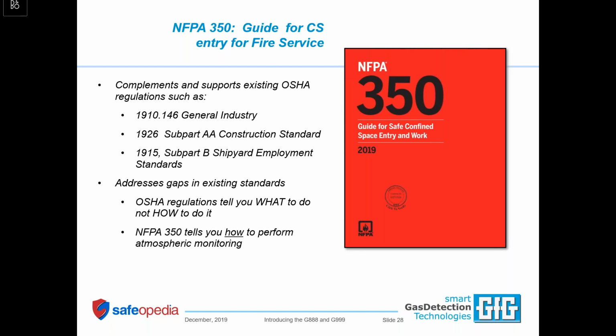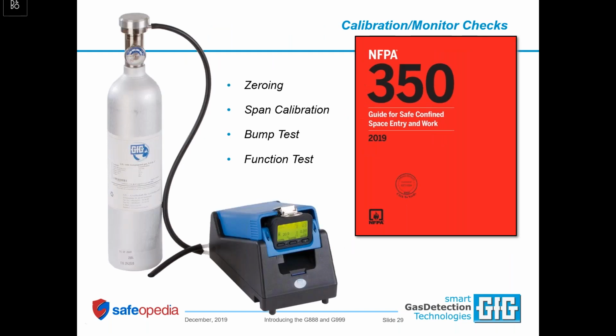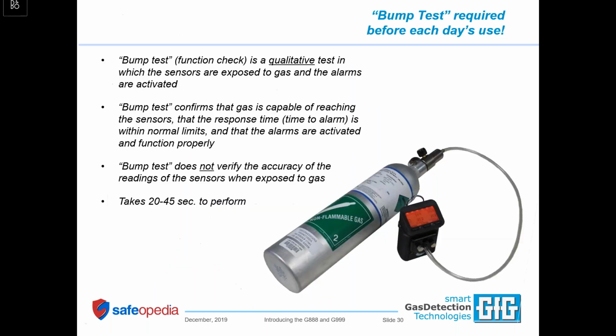Another big change this last year is there's a new edition of NFPA 350, the Fire Service Confined Space Entry Code. NFPA 350 tells you what to do and how to perform tasks related to atmospheric monitoring. It's a very detailed guideline, including requirements for zeroing, span calibration, bump testing, and function testing your instrument. It covers all the bases.